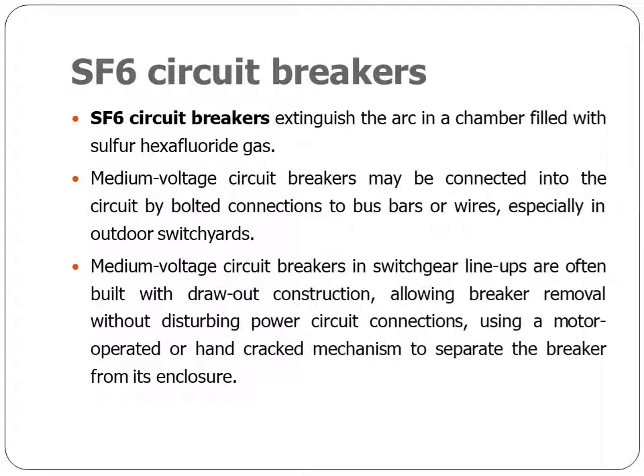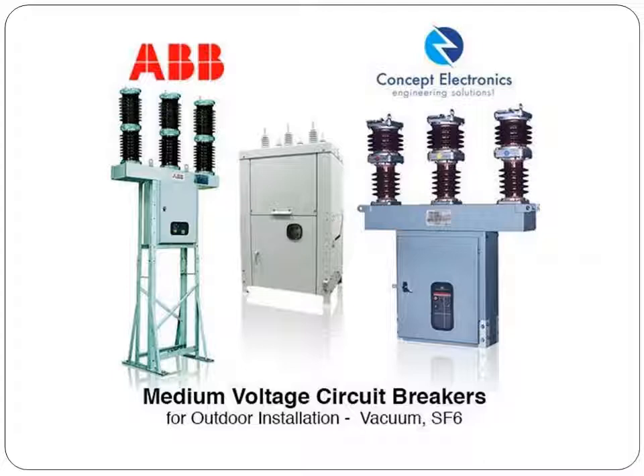Medium voltage circuit breakers may be connected into the circuit by bolted connection to the bus bars or wires, especially in outdoor switchyards. Medium voltage circuit breakers in switchgear lineups are often built with draw-out construction, allowing breaker removal without disturbing power circuit connections, using a motor-operated or hand-cranked mechanism to separate the breaker from its enclosure. So these diagrams illustrate the different medium voltage circuit breakers normally used for outdoor installation. One is vacuum, the second one is SF6, sulfur hexafluoride.